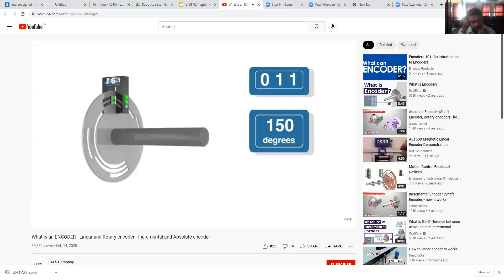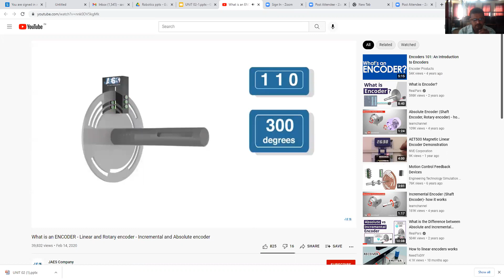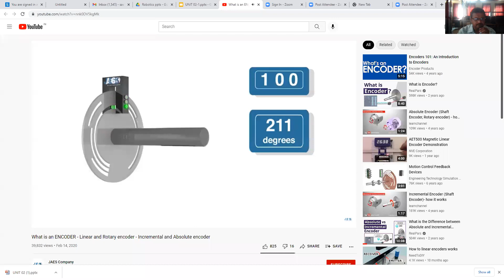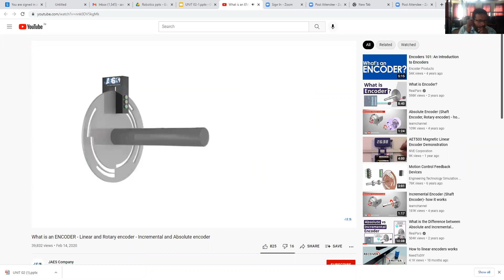This means that each position of the shaft has a pattern, and this pattern is used to determine the exact position. If the power to the encoder was lost and the shaft was rotated, when power is resumed, the encoder will record the absolute position as demonstrated by the unique pattern transmitted by the disk and received by the pickup device. Absolute measurement encoders can be single turn or multi-turn.